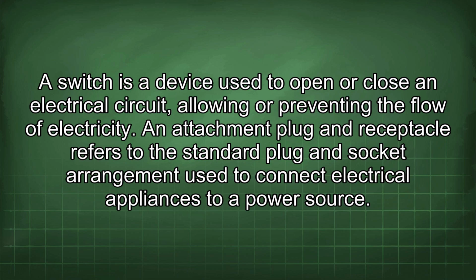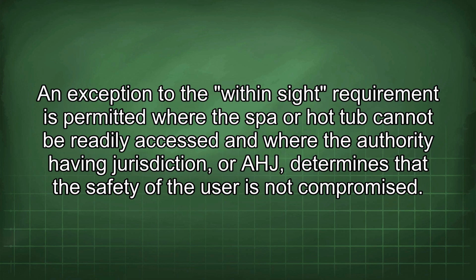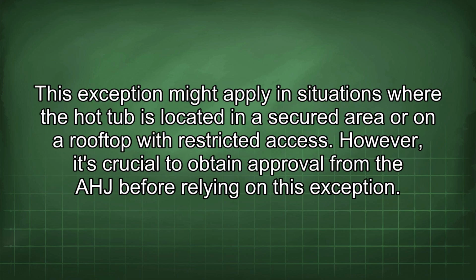An exception to the within-sight requirement is permitted where the spa or hot tub cannot be readily accessed and where the authority having jurisdiction, or AHJ, determines that the safety of the user is not compromised. This exception might apply in situations where the hot tub is located in a secured area or on a rooftop with restricted access. However, it's crucial to obtain approval from the AHJ before relying on this exception.